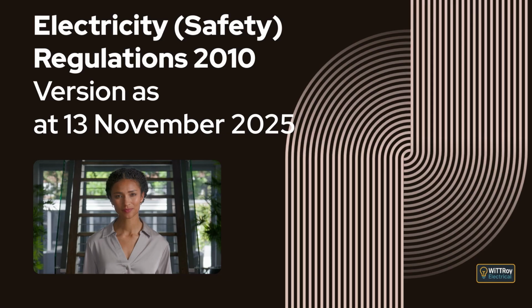The regulation then explains that where electricity is supplied to an installation operating at a voltage other than standard low voltage, calculated or measured at the point of supply, the supply voltage must be a voltage agreed between the electricity retailer and the customer. It further explains that, unless the retailer and the customer agree otherwise, and apart from momentary fluctuations, the supply voltage must be maintained within 10% of the agreed supply voltage. The regulation finishes by explaining that a person who supplies electricity commits an offence and is liable to a Level 2 penalty if they supply electricity to an installation in breach of this regulation.